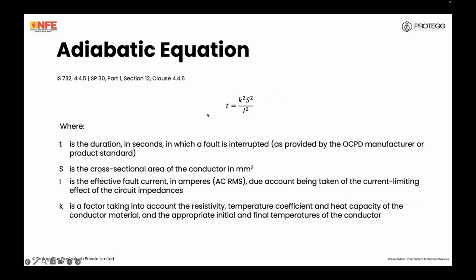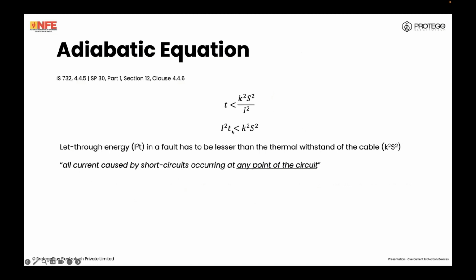So if you remember, we'll just rearrange this equation. I'll show you something magical. And k is a factor that is given in the table for the cable depending on the resistivity, temperature coefficient, and heat capacity. This is in the National Electrical Code. I'll show you. If we rearrange this, we will get that I squared t shall be less than or equal to k squared S squared. If you remember, this I squared t value corresponds to the let-through energy, which is given by the manufacturer of the OCPD.